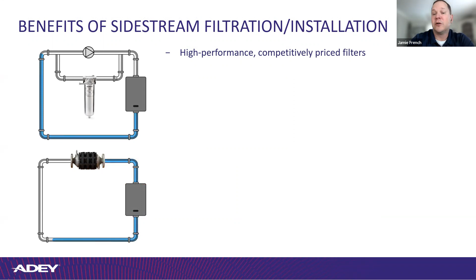And here we go with the side stream. The benefits: you can use a smaller filter, competitively priced based on this. So rather than going in line, you're going around the pump. We'll show that on the next slide. But it's great in a retrofit to replace a chemical shot feeder that's already installed, a good option.